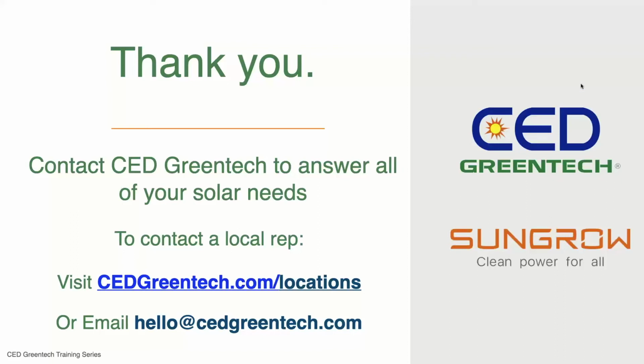So while we do have customers that are still very much in favor of the single power point tracker feature with the SG125 HV, the SG350 is still going to be multiple MPPT for distributed generation. Now, that's not to say that you can't have it installed in a virtual central configuration. If your DC runs are going to be longer in that instance, then you may need to invest in some DC optimizers or DC to DC converters to maintain that DC voltage level over long runs. So it's not entirely impossible. It'll just increase the project cost a little bit.